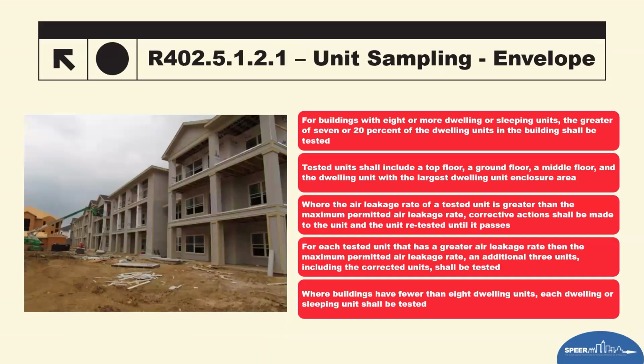Multifamily, they finally pulled in a sampling protocol. So this basically is unit sampling. It provides a balanced way to ensure quality without testing every apartment. The code requires statistically valid sampling. It says at the least of 7 or 20%, whichever is greater, and specifically calls out you have to represent specific floor and unit types. As we read on here, it must include a top floor, ground floor, a middle floor, and then the one that has the largest enclosure area. And where air leakage is tested but exceeds the limit, it must be corrected and retested. Each time that it fails, we must add 3 more units to that sampling group. And then those also must be tested. Any building that has fewer than 8 dwelling units, basically each one of those will be tested.